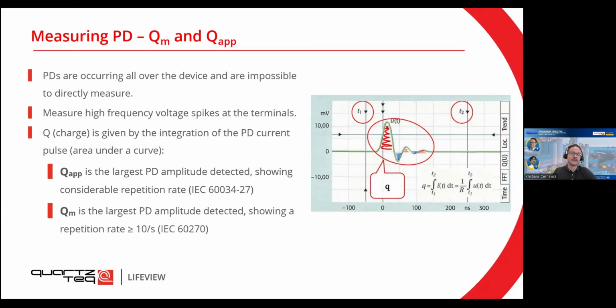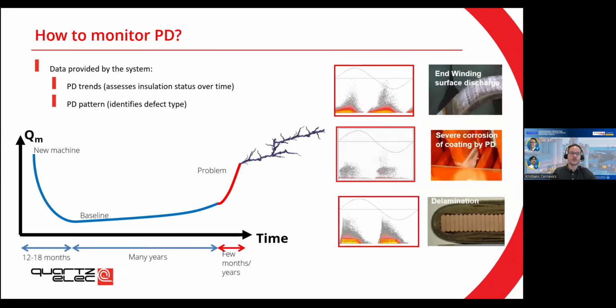What we can do then is integrate these voltage spikes to get a value of charge. And this is essentially standardized by the IEC standards. So QM and QAP charges can be compared between different machines. This gives us a nice quantitative way to capture the magnitude of the PD discharges. Usually the systems would provide you two different views. First of all, the PD trend: how does the magnitude of discharge increase with time? And the other one is the PD pattern, which would tell you the type of defect that is happening in your machine. If we look on the right at these three graphs with the PD patterns, each of the points is a discharge that I showed you in the previous slide.